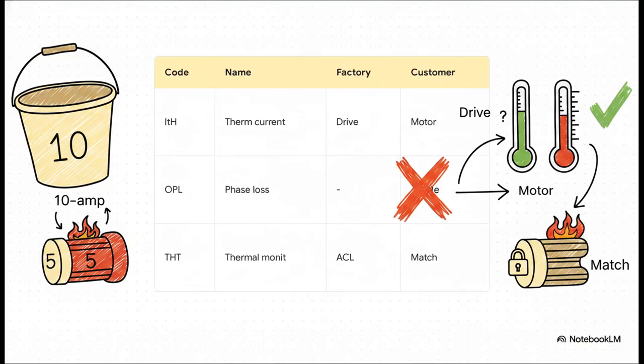Moving right along to Section 2, Key Protection Parameters and the real danger of relying on defaults. Okay, let's uncover a very costly mistake that's hiding in the factory settings. This right here is where perfectly good motors end up getting destroyed, just because someone assumed the drive was protecting the motor straight out of the box. Look closely at the ITH parameter. That's your motor thermal current. Check out the factory setting. It defaults to the maximum drive rating. Let me tell you why that's so dangerous.